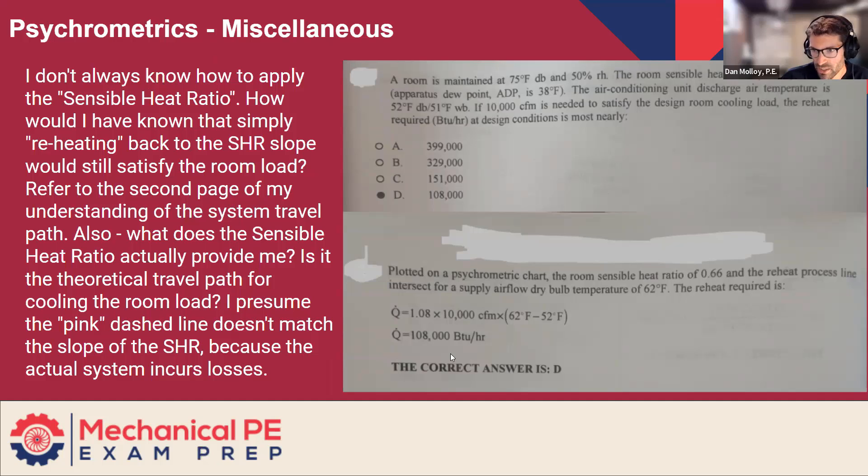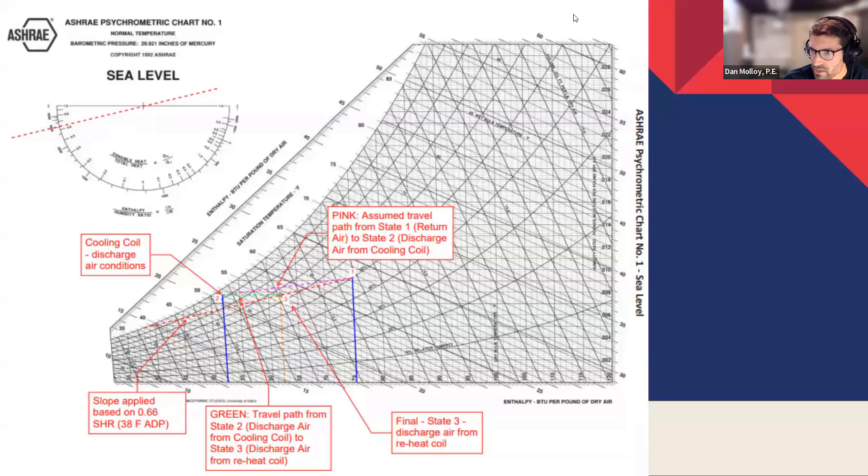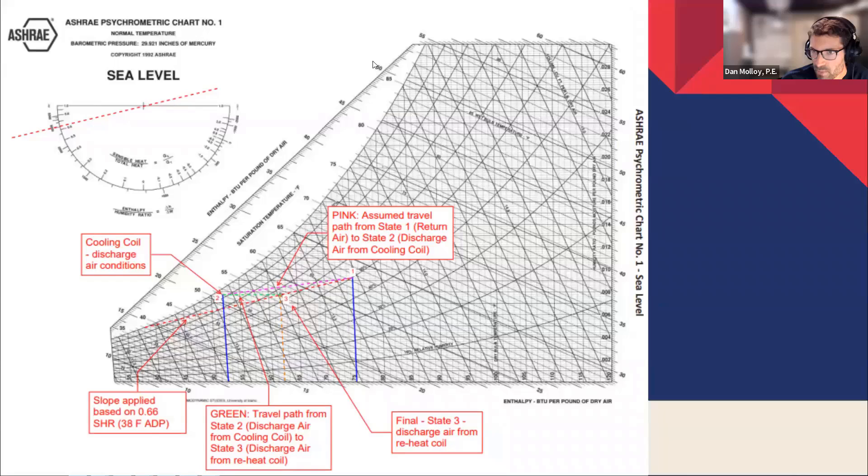And the solution, they have us draw the sensible heat ratio line and also a line from the room condition to the supply condition. And it's the reheat that we're being asked to quantify. And they end up using 1.08 CFM delta T to find out what that quantity of reheat is. But the question here is like, how am I supposed to know that the reheat is the distance between the discharge air temperature point and the SHR line? And let's go to the picture to kind of answer that. It's probably the best way. And maybe I can even darken some of the lines that you drew here. Did a nice job showing this.